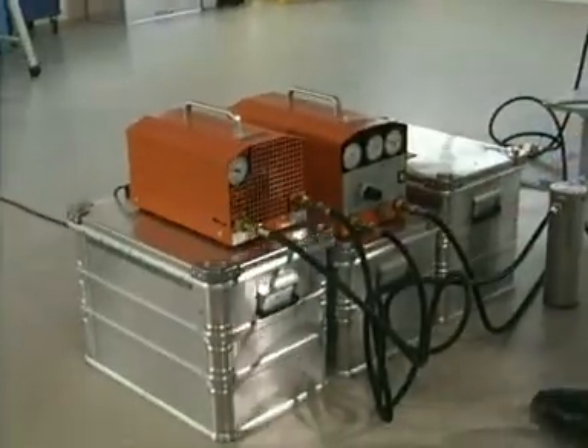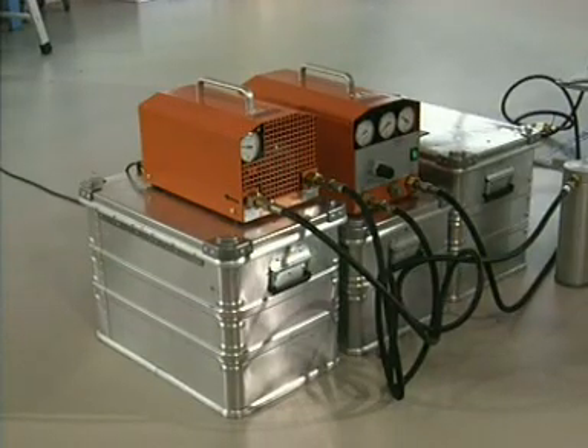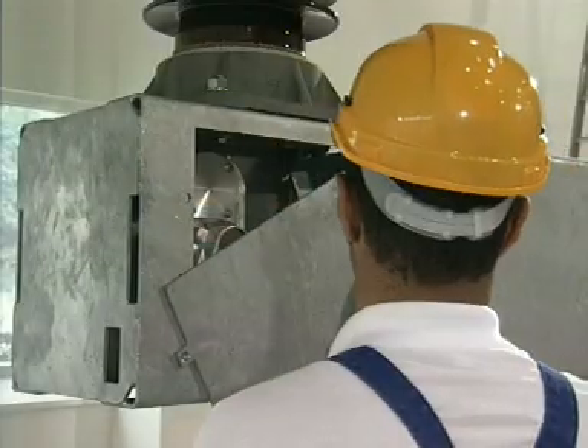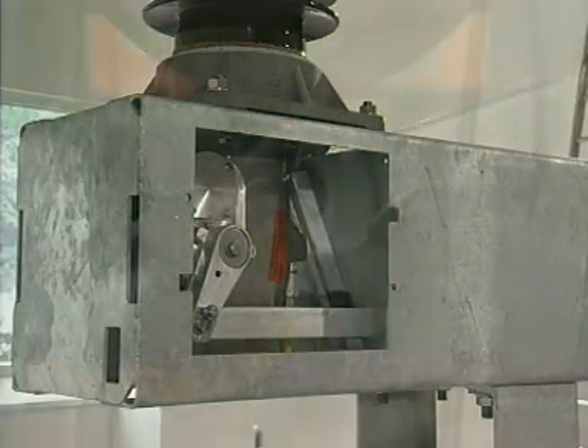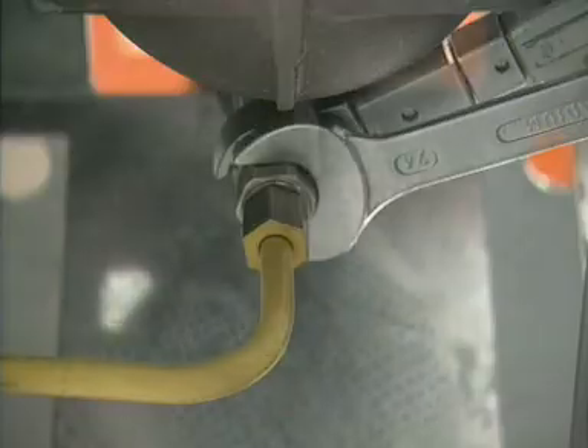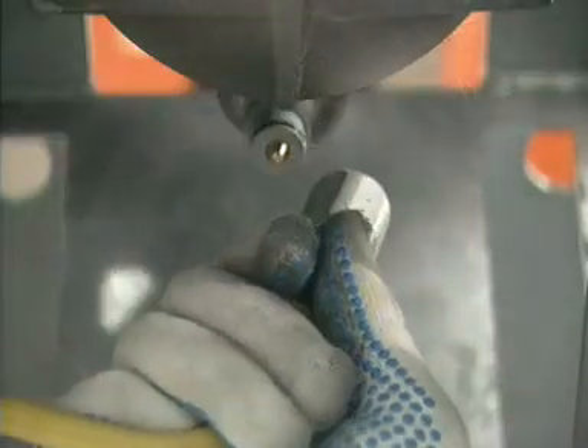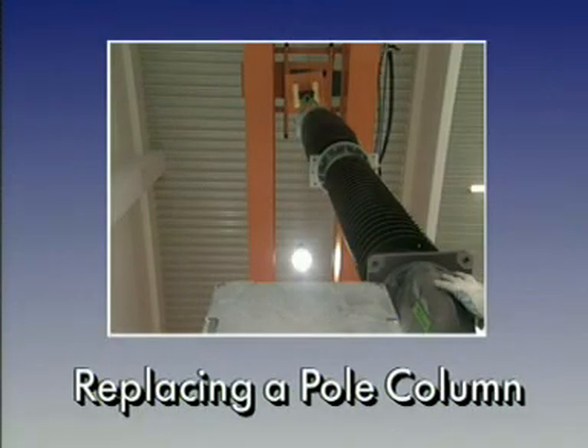Evacuate the SF6 gas through an additional filter using a gas handling device such as a gas cart. Remove the covers of the installation openings in the base frame. Detach the SF6 piping system from all 3 pole columns and vent the pole columns until the pressure has been equalized.